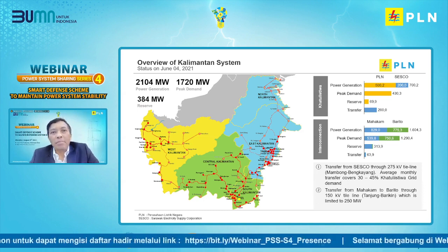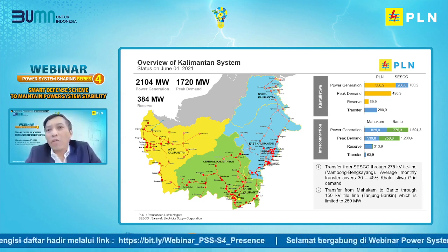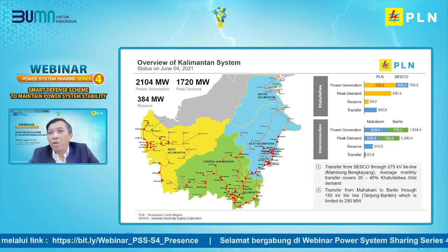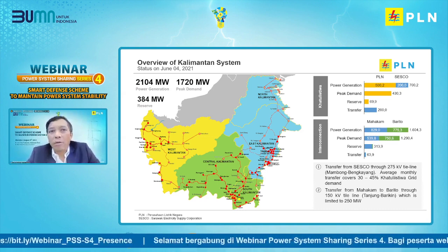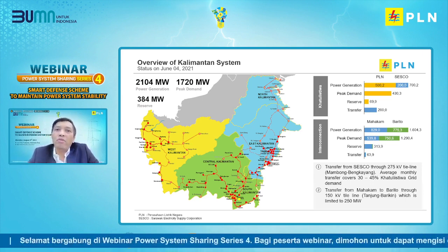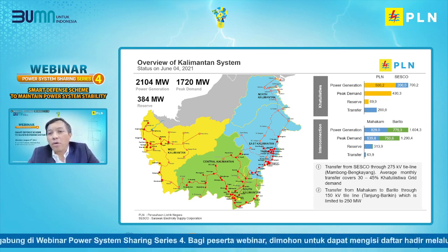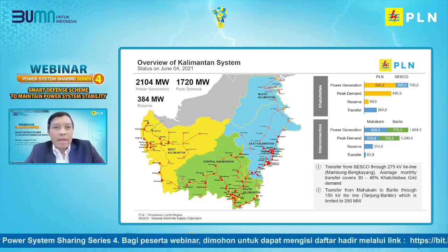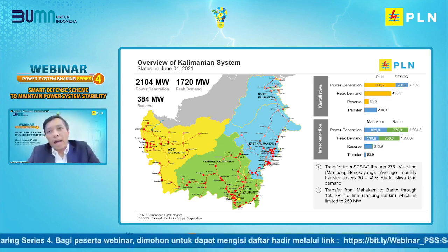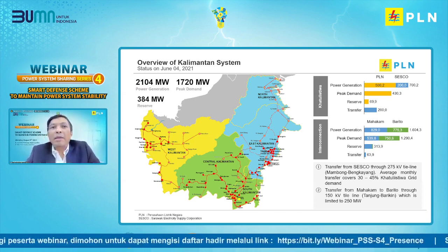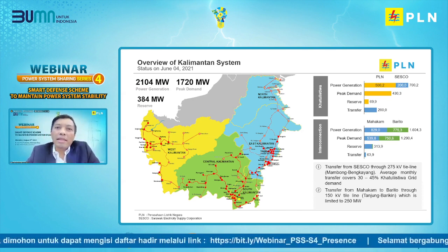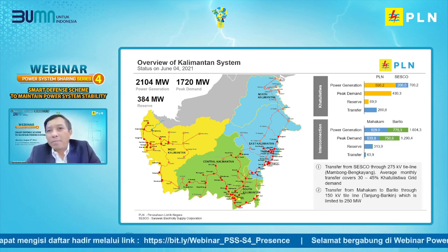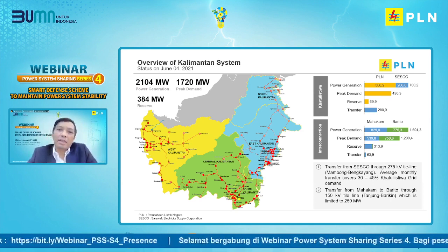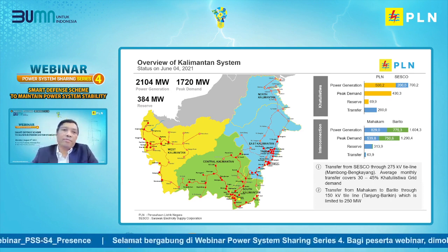The Khatulistiwa system is interconnected with SESCO Sarawak grid system via 275 kV network. The supply from SESCO covers around 30 to 45% of the total load of Khatulistiwa grid. Interconnection system consists of Mahakam subsystem in East Kalimantan and Barito subsystem in South Kalimantan and Central Kalimantan. The subsystems are connected via Tanjung Barikin line, which has maximum carrying capacity around 250 megawatt.